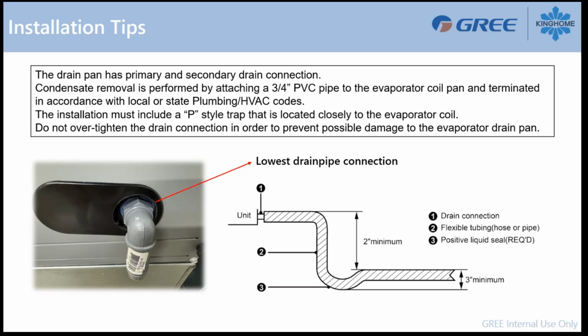And also, you see here on the picture, we have some black covers over the drain pan. So we have four like this one. If you look at the picture, there's a little slope to the right on this drain pan connection. So always make sure you take the lowest connection to connect your drain. So obviously this is an upflow air handler installation, so you use the right side connection here. And also I used a small bit just to drill my hole and make a good connection here. So my 3/4 PVC pipe here can fit perfectly inside, and there's no leakage, and it's done. It will do a great job.